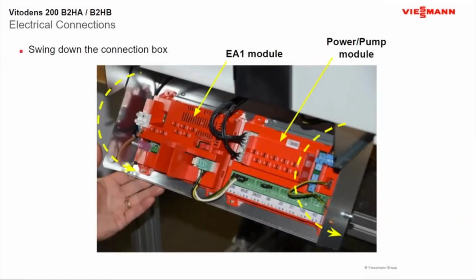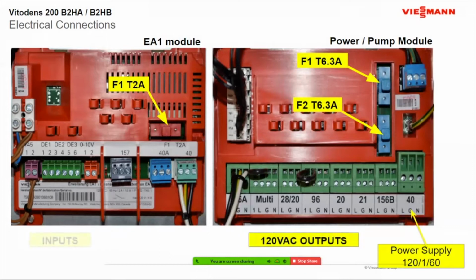Once you get the cover off the boiler, down below there's a box. And normally there's going to be 2 screws in the front of this with a cover on it, and then 2 screws on the side, and it allows you to pull it out and let it slide down so you can work on all your wiring. Let's go over our wiring once we fold that cover down. As you can see, this is exactly what you would be looking at right at that control box when you folded it down. So on the right-hand side is mostly where all your line voltage is going to go, your pump outputs, your incoming power, things to that nature.